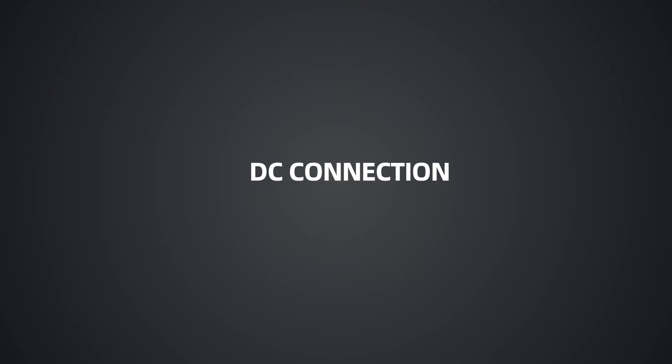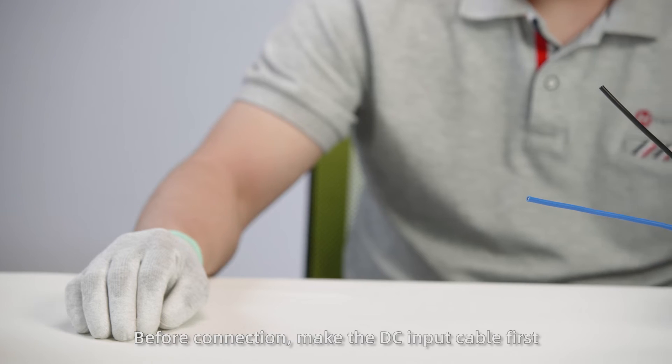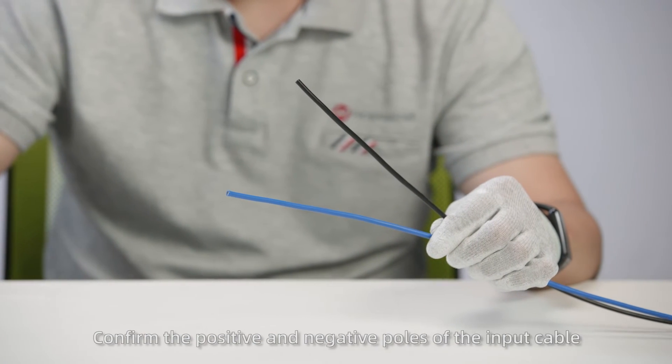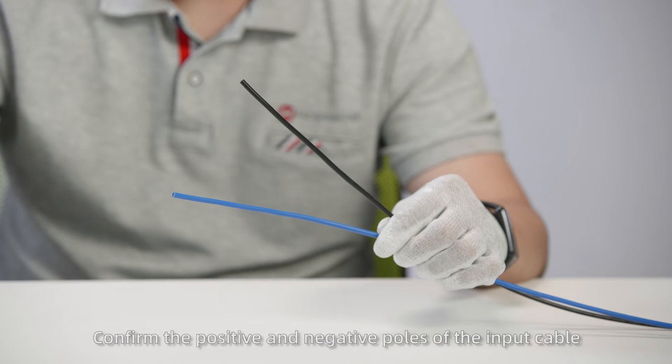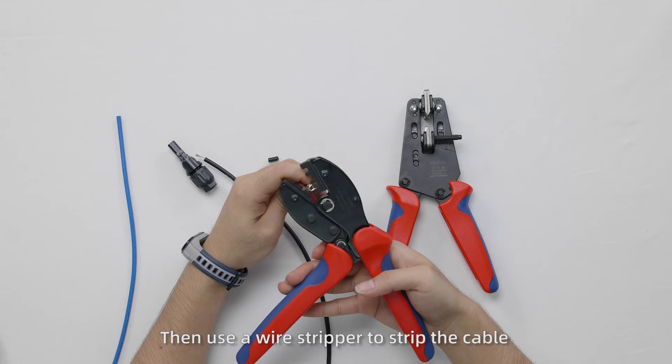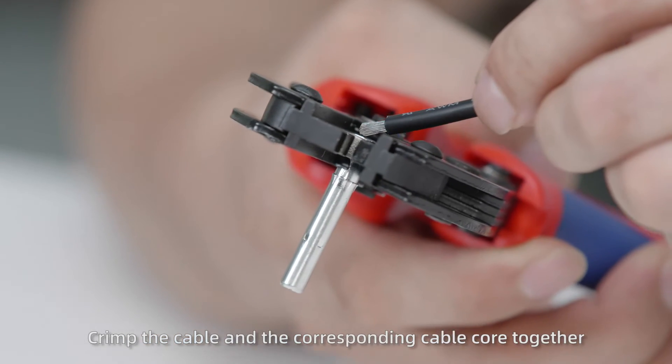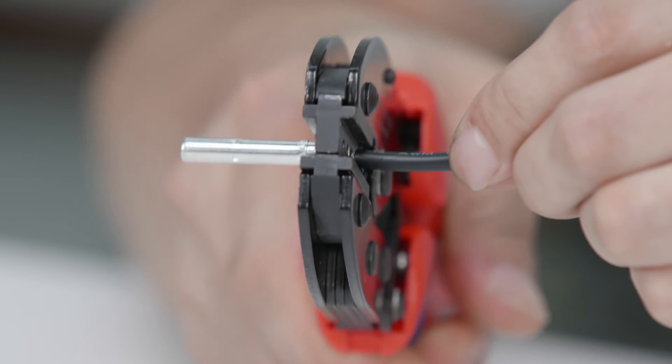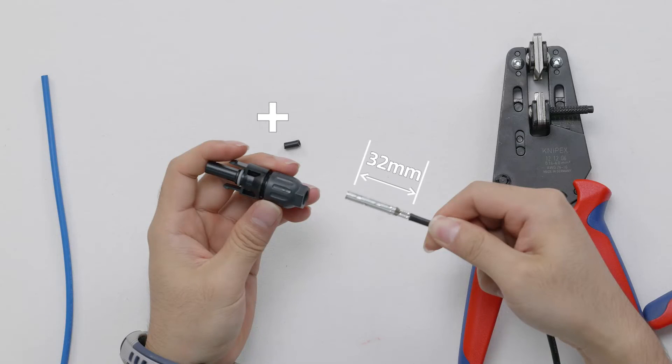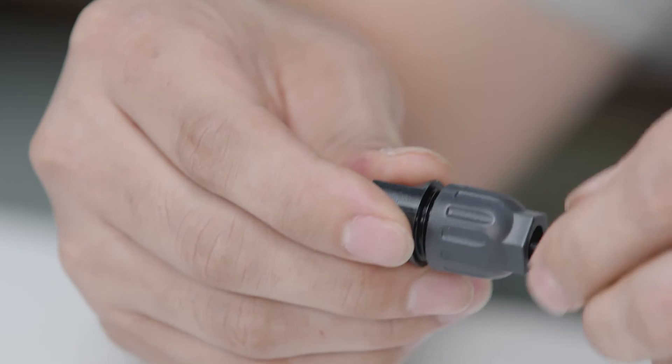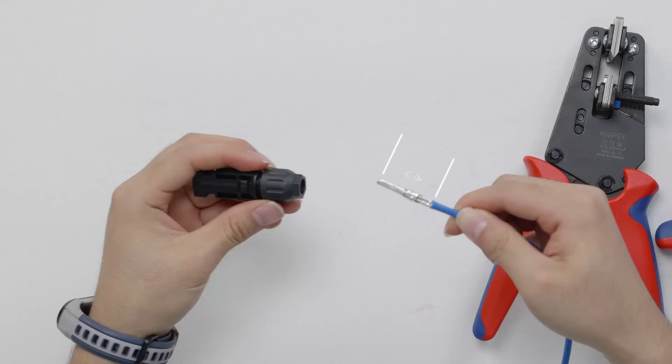Finally, connect cables on the DC side. Before connection, make the DC input cable first. Confirm the positive and negative poles of the input cable. Use a wire stripper to strip the cable. Crimp the cable and the corresponding cable core together. Finally insert the cable core into the male and female poles of the MC4 connector according to the correct polarity and tighten the back cover.